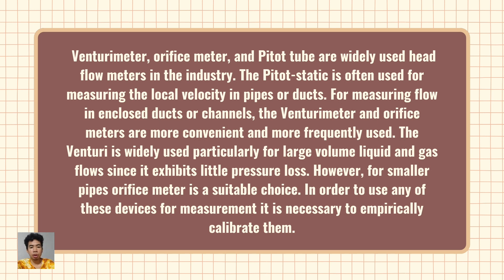Venturimeter, orifice meter, and pitot tube are widely used head flow meters in the industry. The pitot static is often used for measuring the local velocity in pipes or ducts. For measuring flow in enclosed ducts or channels, the Venturimeter and orifice meters are more convenient and more frequently used. The Venturi is widely used particularly for large volume liquid and gas flow since it exhibits little pressure loss.